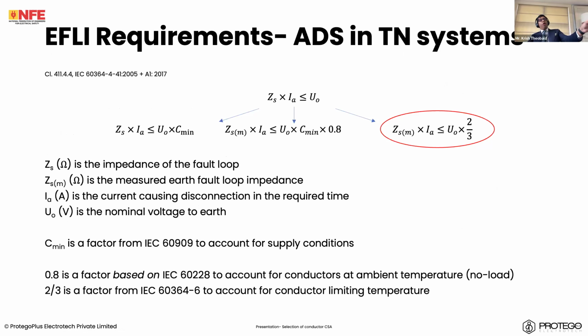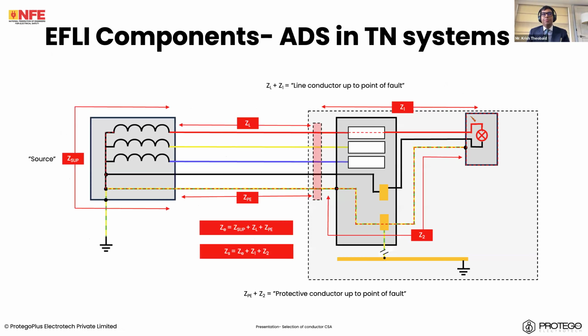Okay, now earth fault loop impedance, everybody's favorite subject. The idea of earth fault loop impedance is: is the device going to cause disconnection in the required time such that protection against electric shock is ensured? I'll show you an image. We consider this installation. This is our supply or our source. This is our conductor flowing in the distribution system. This is our installation, the point of commencement of supply. And the conductor flows from the point of commencement of supply to the load, and from the area of the fault back to the point of commencement of supply and back to the source.